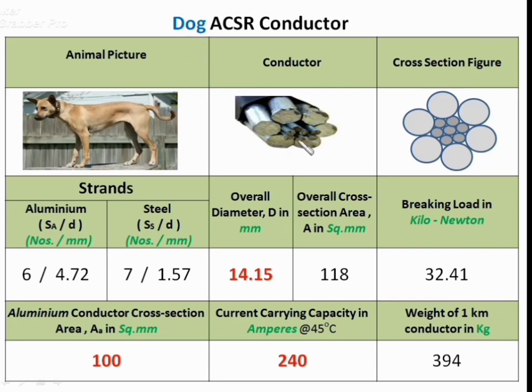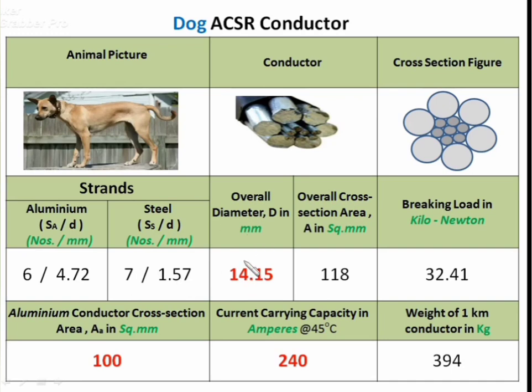The conductor cross-section looks like this: internal strands are steel and the outer ones are aluminium. The aluminium strands are six in number with 4.72 mm diameter; steel strands are seven with 1.57 mm diameter. Overall diameter is 14.15 mm. Total cross-section area of the conductor is 118 mm², breaking load is 32.41 kN, and only aluminium conductor cross-section area is 100 mm².